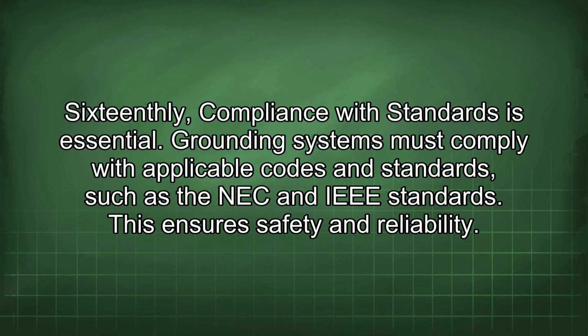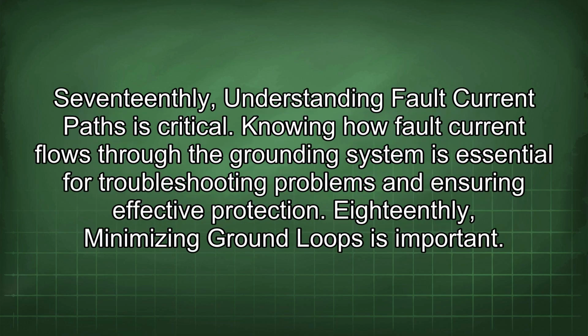Sixteenthly, compliance with standards is essential. Grounding systems must comply with applicable codes and standards such as the NEC and IEEE standards. This ensures safety and reliability. Seventeenthly, understanding fault current paths is critical. Knowing how fault current flows through the grounding system is essential for troubleshooting problems and ensuring effective protection.